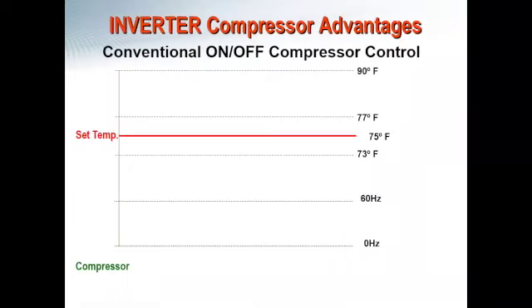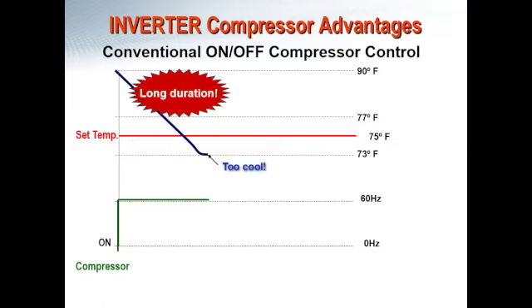So this next slide here, we're going to start talking about the differences in compressor between a conventional HVAC system and a VRF HVAC system. I'm sure most of you are familiar with the way a conventional compressor on a traditional system would work. It's on-off compressor control only. This slide is showing linearly the temperature in the space. We have a set temperature we're trying to achieve of 75 degrees Fahrenheit. We're going to start off at 90 degrees in the space. This may be coming back after a long hot summer weekend, something like that.